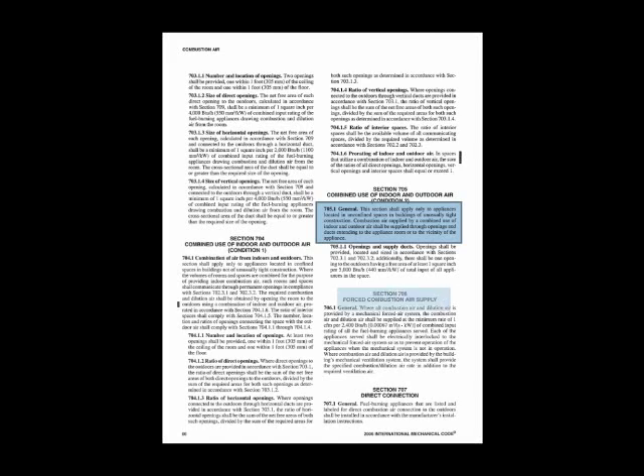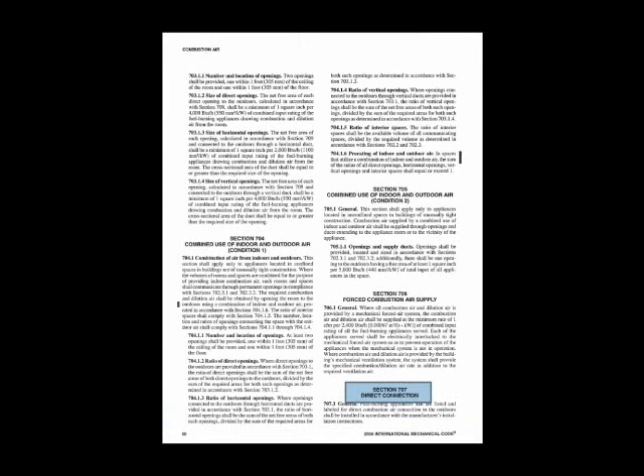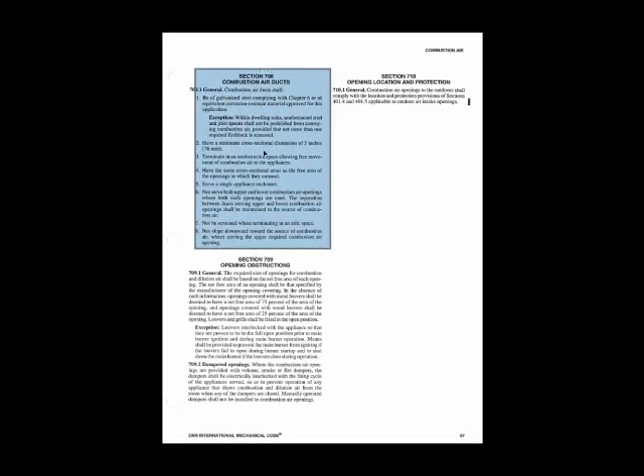706 talks about forced combustion air supply. In other words, if I use a motor and a fan to push combustion air into an area. 707 talks about a direct connection. Let's say I put a vent directly onto the intake side of an oil burner. It's direct connections to combustion air. 708 talks about combustion air ducts. What can I use for my combustion ducts? They have to be of galvanized steel. They have to comply with Chapter 6 of the code. Have to have a minimum cross-sectional dimension of 3 inches. It's to terminate in unobstructed space. Have to have free movement of air. It can't be screened when terminating in an attic space. It cannot slope downwards toward the source of combustion air because we don't want condensation to build up. We don't want a downward slope where moisture goes outside and freezes.